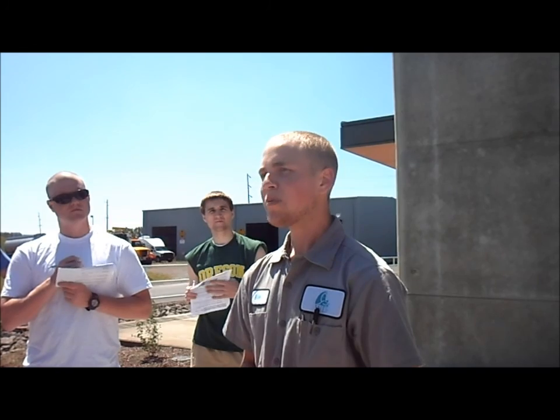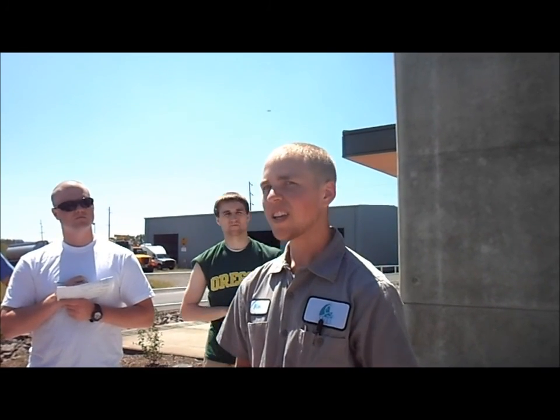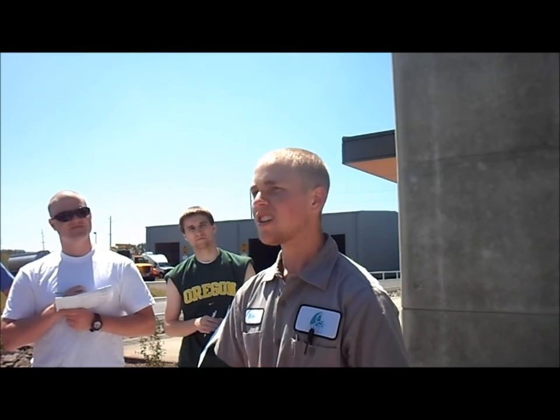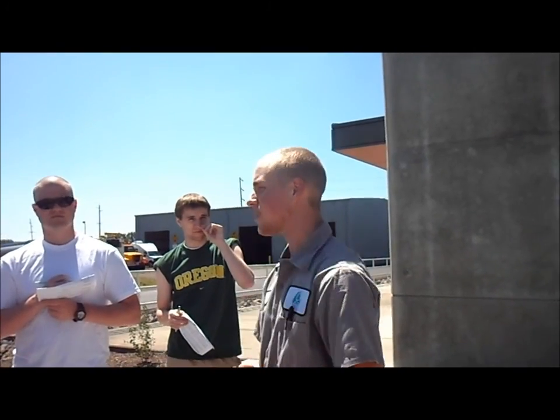So we're putting out NTUs of less than 1. Wow. When they get to 0.1, we know it's time to clean our turbidity meters because we know the water's not that dirty. Usually they're around 0.05, 0.04. Yeah, so they do a tremendous job.